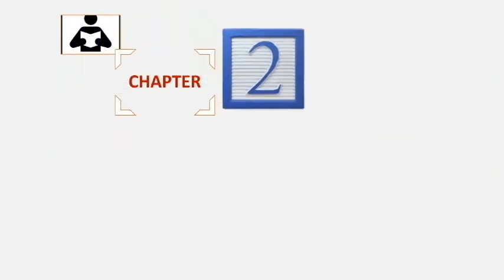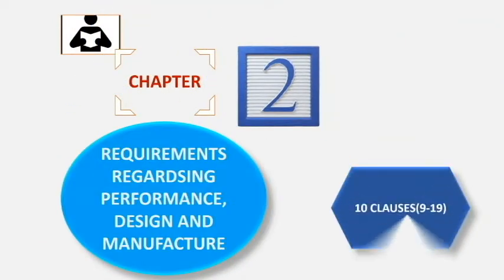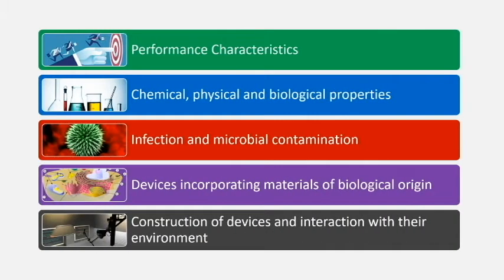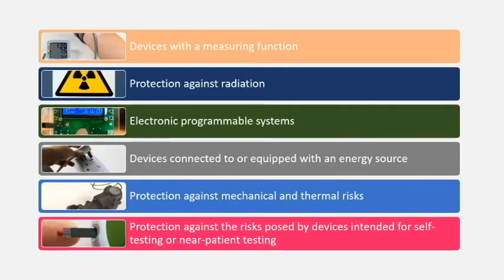Chapter 2 covers requirements regarding performance and has ten clauses — a new criteria added in the GSPR. Under Chapter 2 we look into: performance characteristics, chemical, physical and biological properties, infection and microbial contamination, devices incorporating materials of biological origin, construction of devices and interaction with their environment, devices with a measuring function, protection against radiation, electronic programmable systems, devices connected to or equipped with an energy source, protection against mechanical and thermal risk, and risks posed by devices intended for self-testing or near-patient testing.